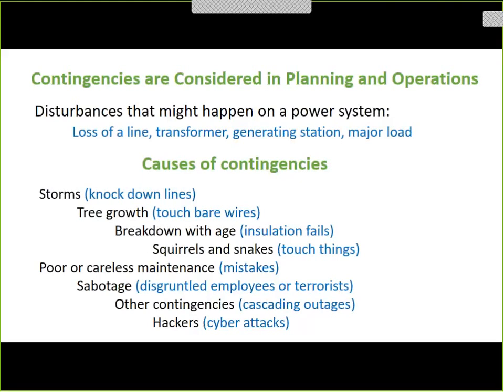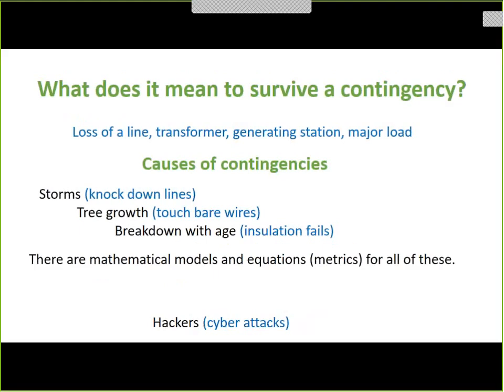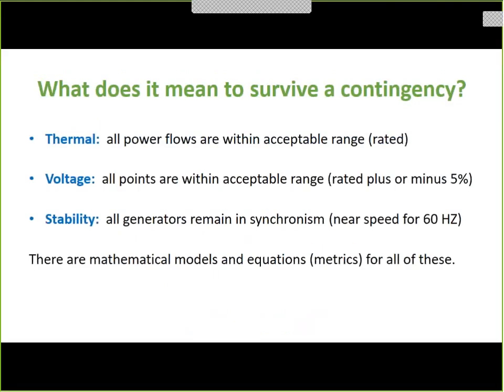What are the causes of contingencies? Here's my favorite list. Of course, ice storms, lightning, tree growth. That was a 2003 instigating problem. The trees grew into the wires and created a short circuit. Insulation could fail because it's old. Squirrels and snakes, they're really sneaky creatures, and they go where they're not supposed to go, and they cause short circuits. Bad maintenance, mistakes, somebody forgetting to take something off, sabotage, disgruntled employees and terrorists, cascading outages, one thing causes another, that causes another, and then, of course, there's always the hackers, the cyber people, and we know about this from the Crimean incident. And we'll hear more about it, I'm sure, in the future.